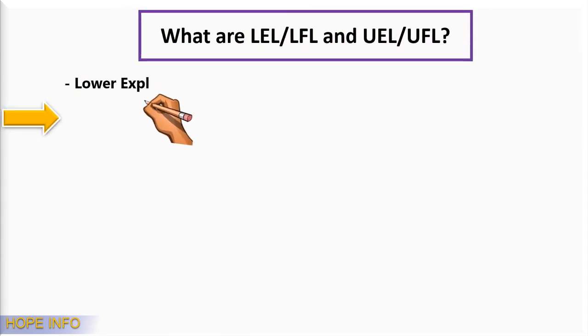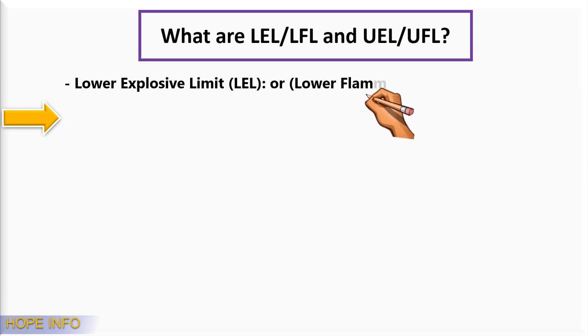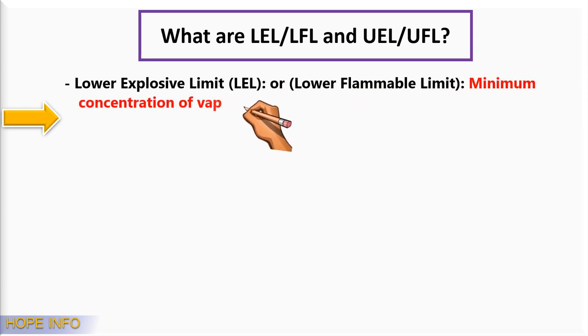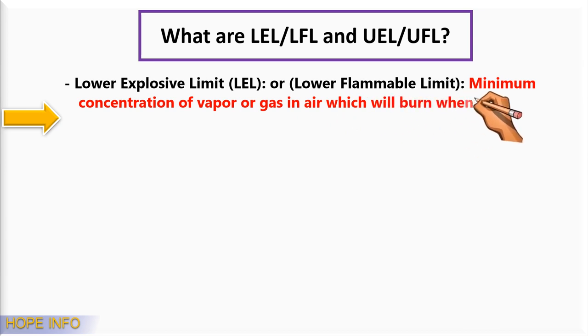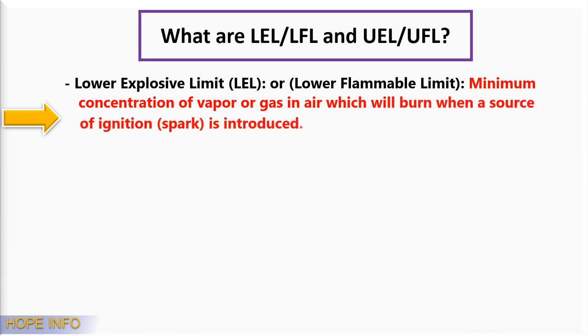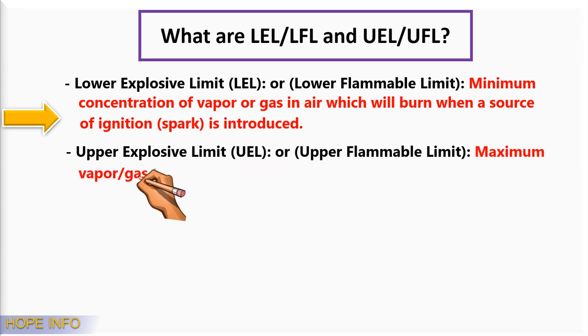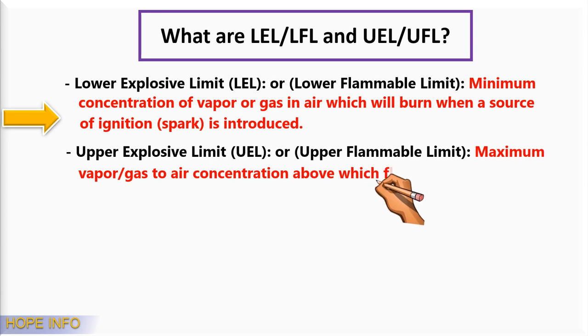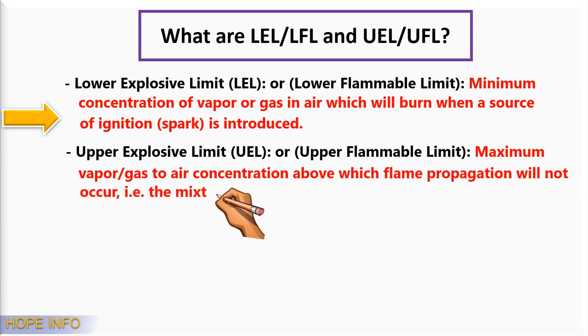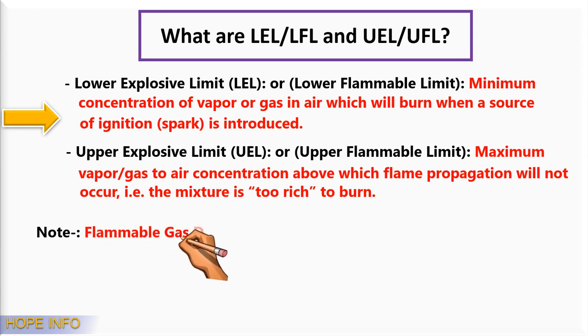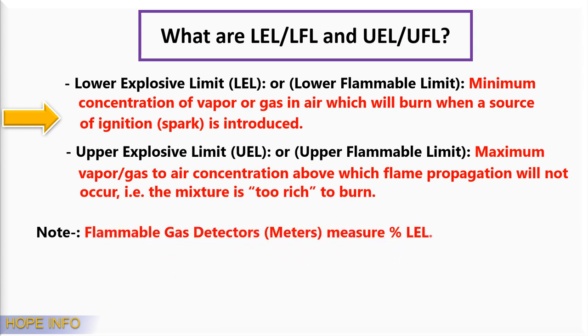What are the LEL, LFL, UEL, and UFL? Lower explosive limit (LEL) or lower flammable limit (LFL): the minimum concentration of vapor or gas in air which will burn when a source of ignition is introduced. Upper explosive limit (UEL) or upper flammable limit (UFL): the maximum vapor or gas to air concentration above which flame propagation will not occur — the mixture is too rich to burn. Note: flammable gas detector meters measure the percentage of LEL.